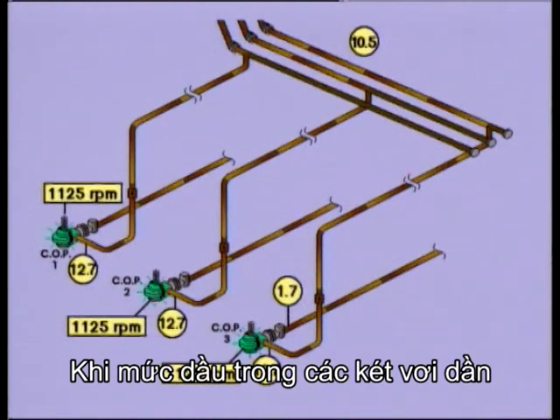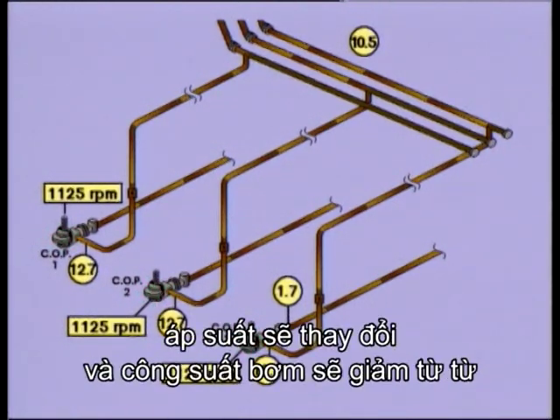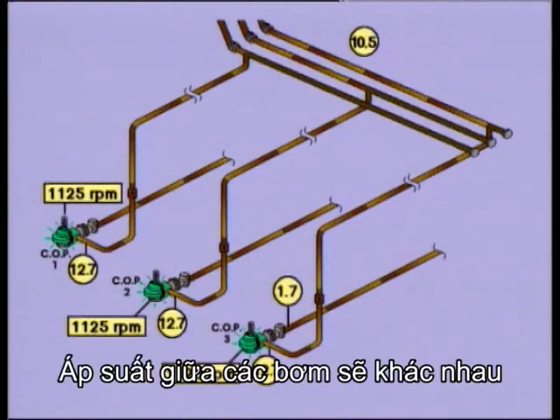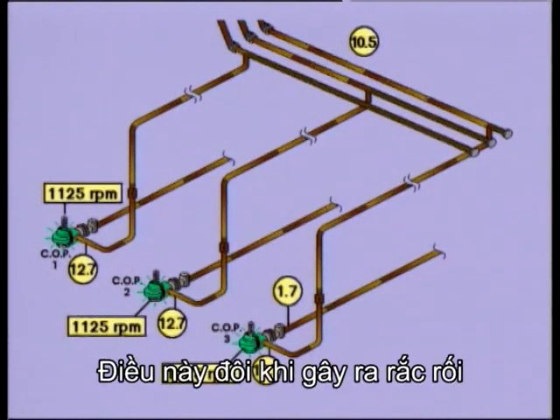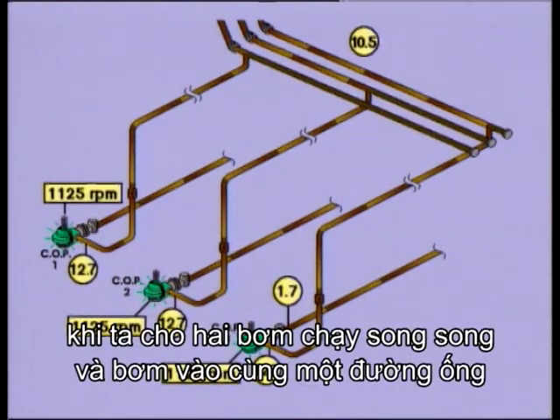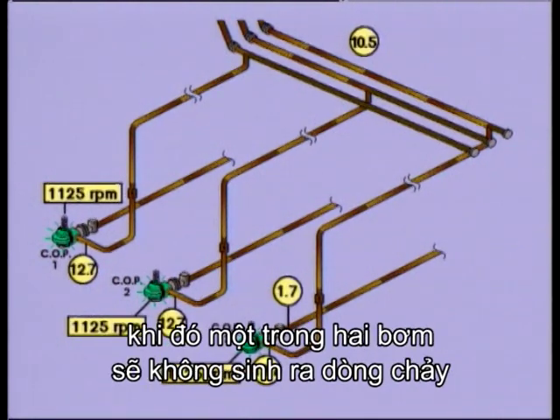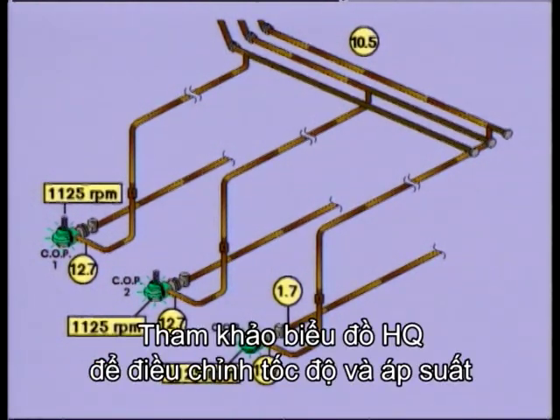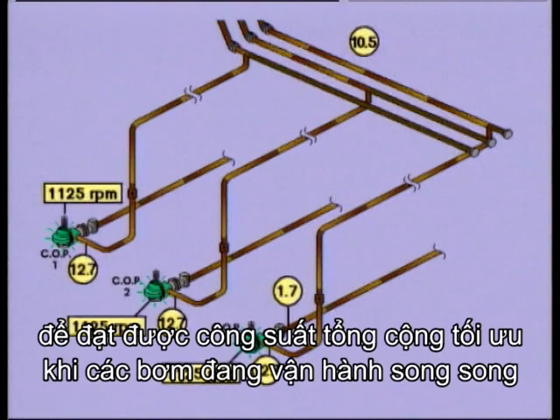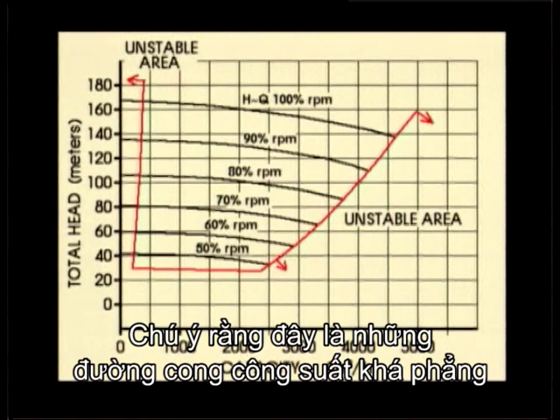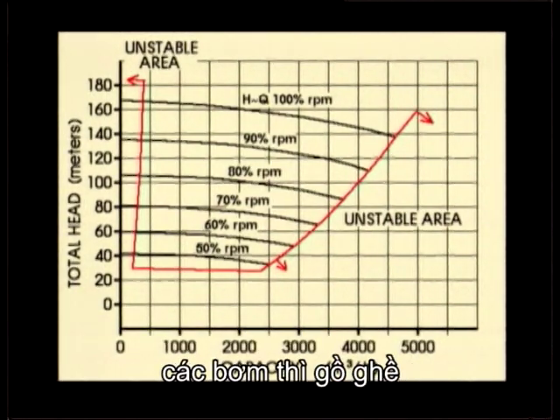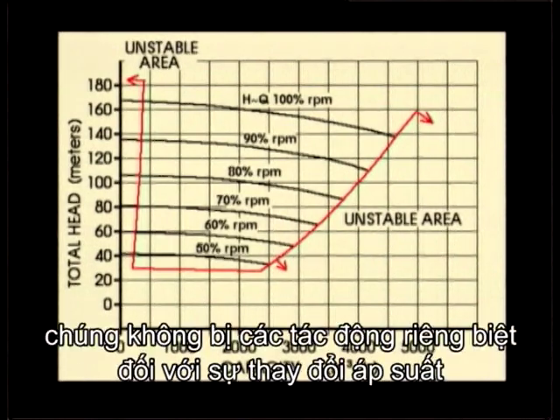As the levels in the tanks get lower, pressures will change and the capacity of the pumps will gradually be reduced. The pressure of the pumps will differ. This will sometimes create problems in running them parallel to the same line, as one pump may not give any flow. Consult the HQ curve to adjust speed and the pressures for optimum total capacity of pumps running in parallel. Note that these capacity curves are quite flat. These pumps are rugged. While running in parallel, they're not particularly sensitive to different pressures.